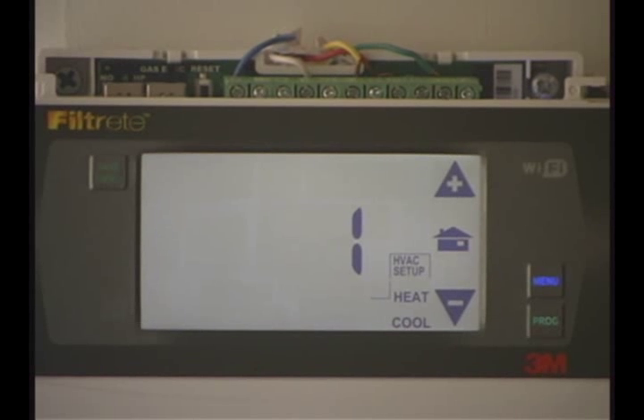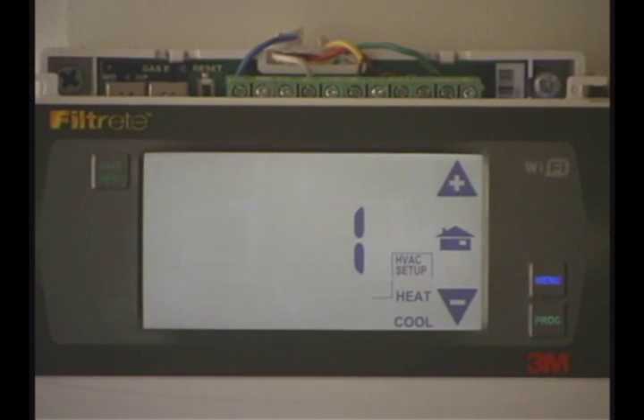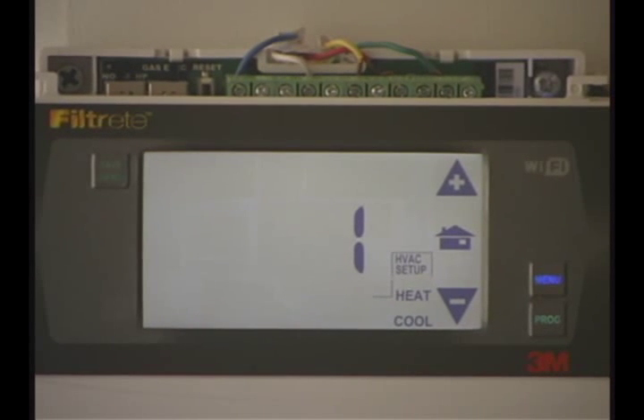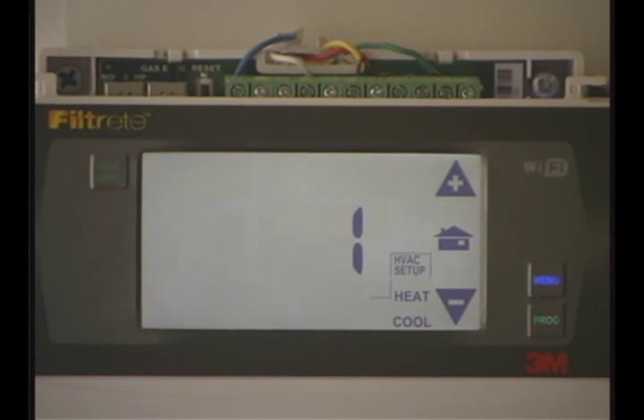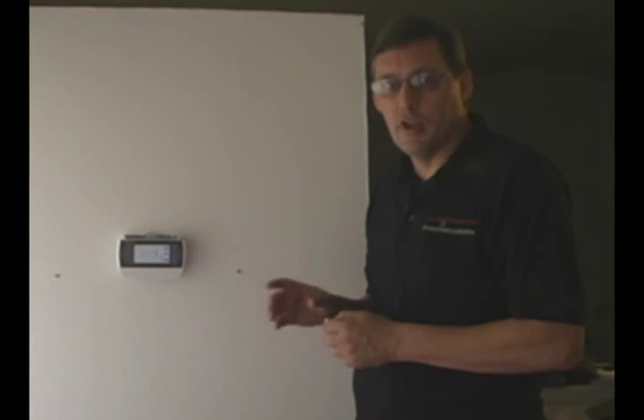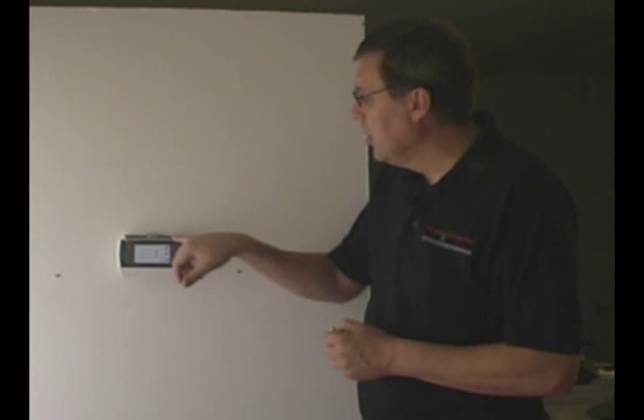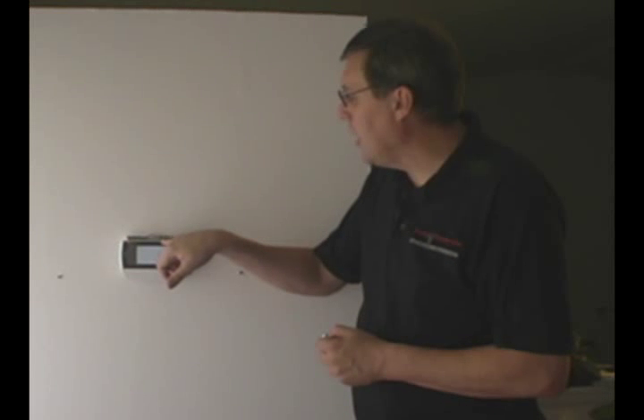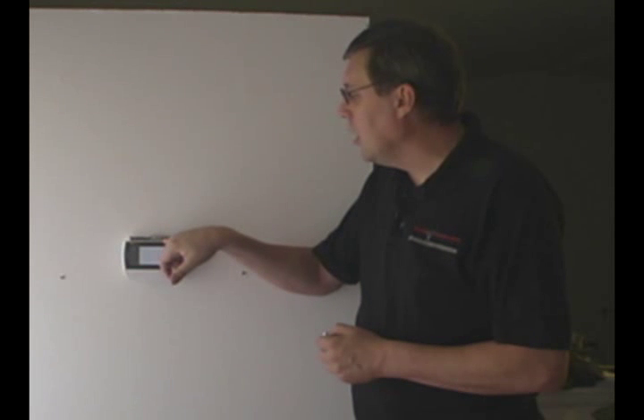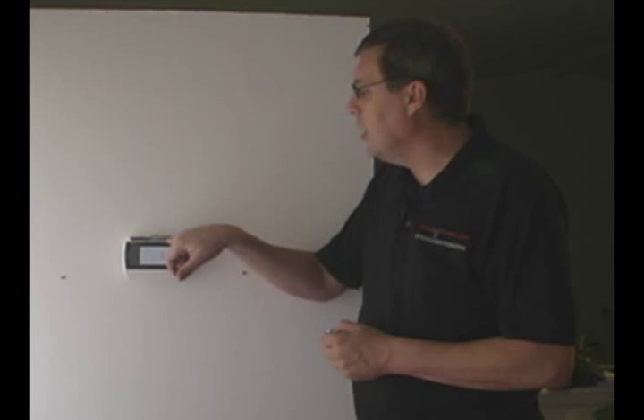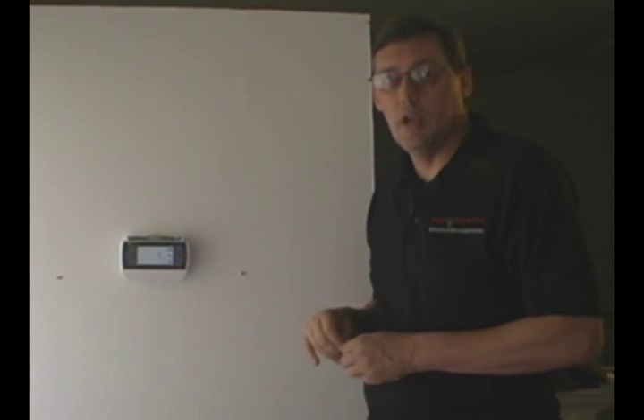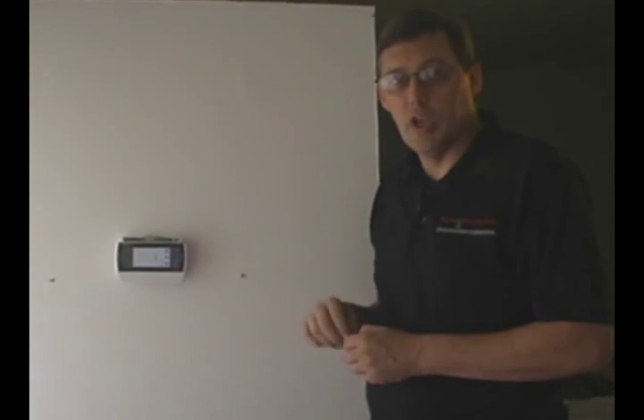Number 1 is set if you have a standard single stage heat and cool — that means you have a furnace and air conditioner. It's a single stage. You would have 4 wires: an R wire, a Y, a W, and possibly a G, and your C.